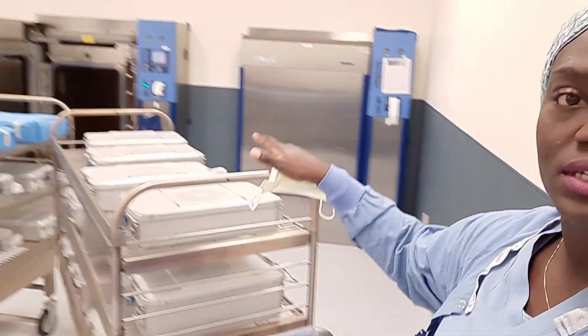So the sterilizer, again, sterilizers, they get tested. I did my test already, and I'll show you that. If you have a 24-hour facility, they get tested at midnight. And if you have a same-day facility, that means patients don't stay overnight, they get tested first thing in the morning. So before you do anything, you have to test the machines. Okay. And then after it's tested and it passes the test, then you can load it up.